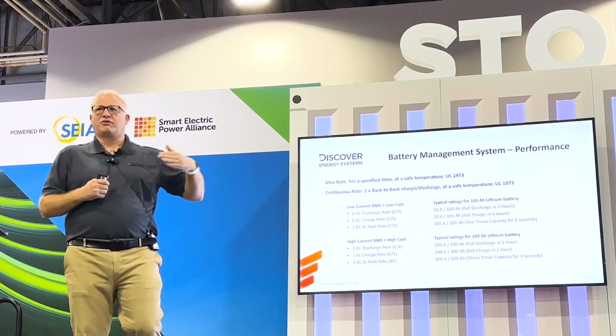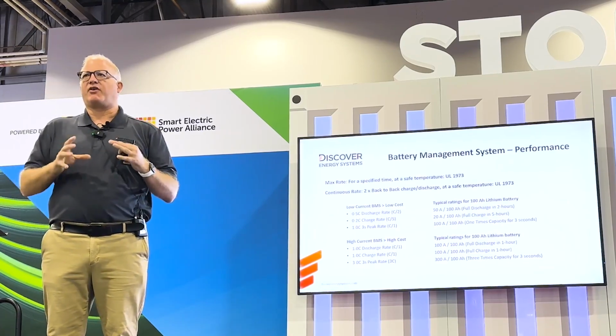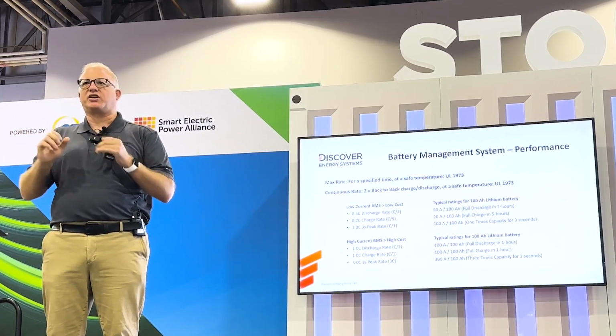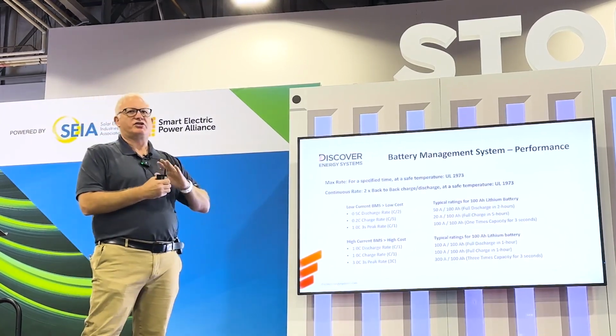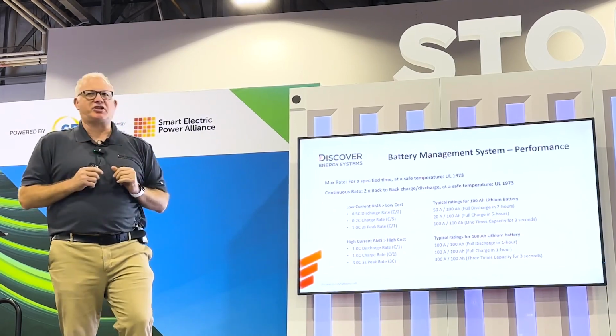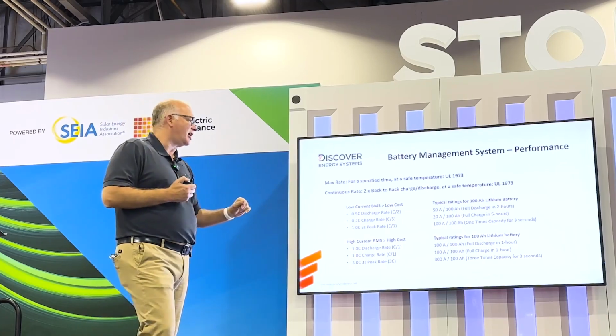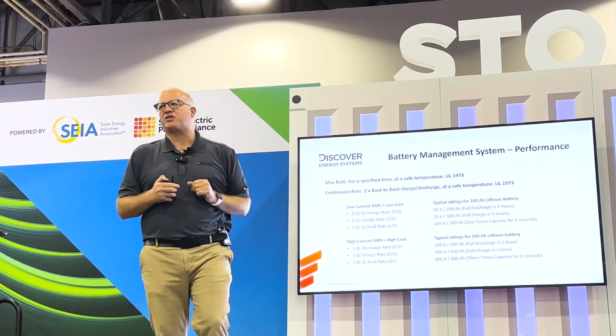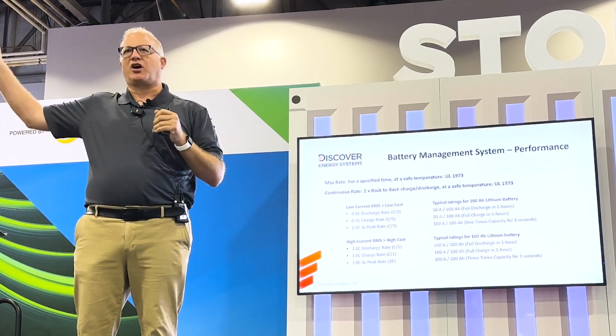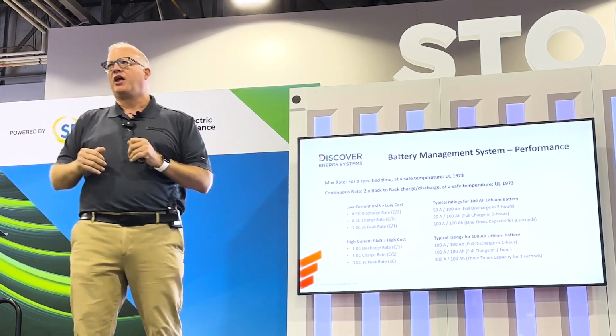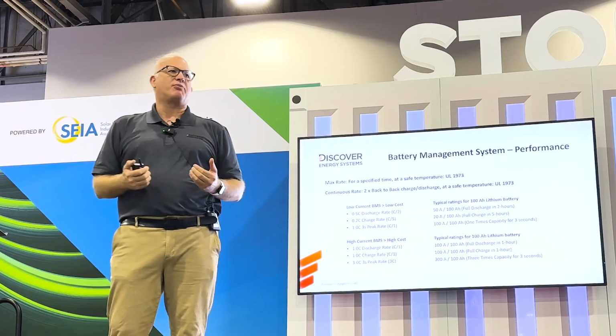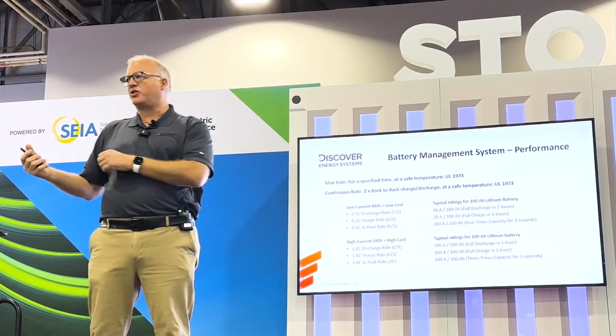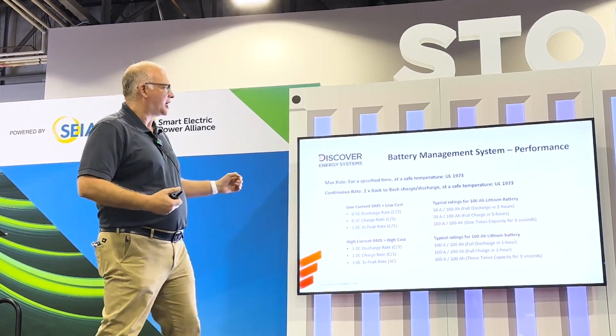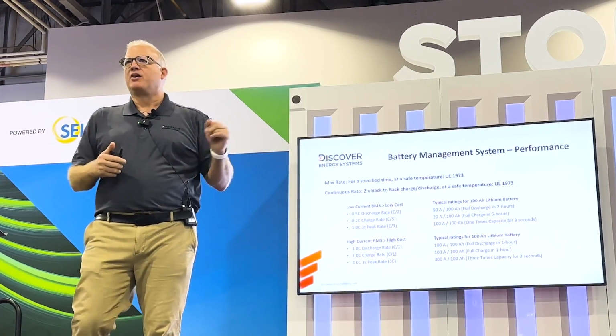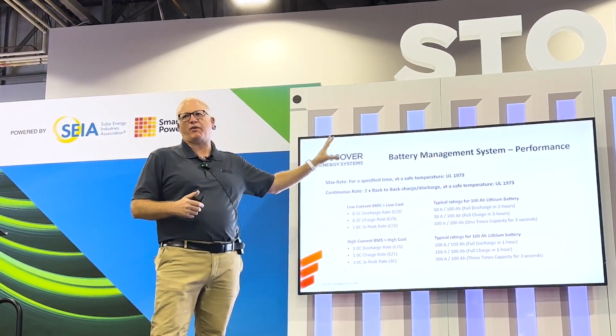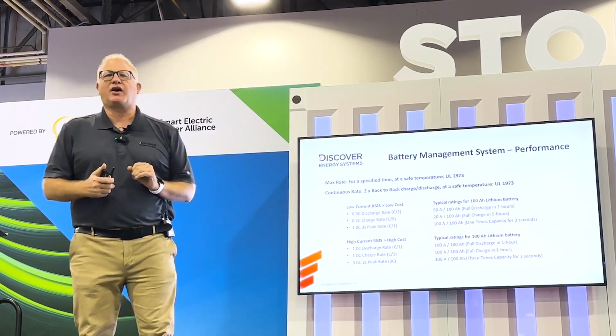In the past, data sheets showed a lot of max continuous power, 1C, 2C, whatever it is. This is going to start to separate into two. There's going to be a continuous rate, and under the safety regulations, UL is beginning to define that as two back-to-back cycles—charge, discharge, discharge, fully, 100%. The battery has to maintain safe operation under test, typically measured by temperature staying within limits. If you can't do that, you can't get 1973. So that's going to become our continuous rate, and we'll all probably have to put that on our data sheets to be accepted by UL.